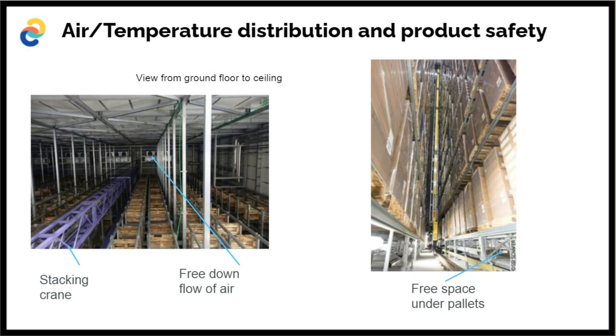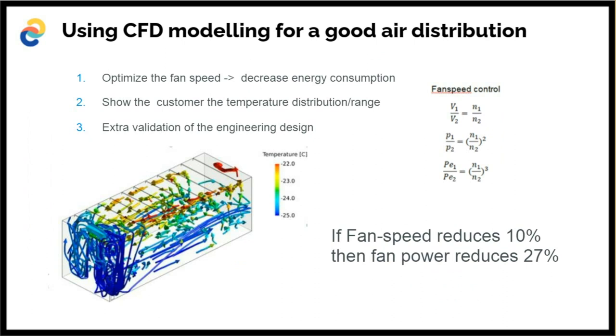We are now at one end and we are looking up, and we see here the fans of the coolers blowing down. That has to be completely free, and the air must flow nicely and not be disturbed by the stacking cranes. And we need some free space under the pallets, like you see here on the right one. So during the construction of the high bay, you need to take that into account, that there is a free flow of air. Now, if we do that nicely with the CFD modeling system, we can absolutely minimize the fan speed and we can reduce fan power.